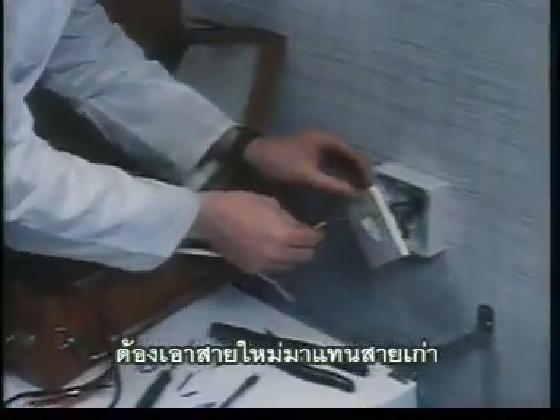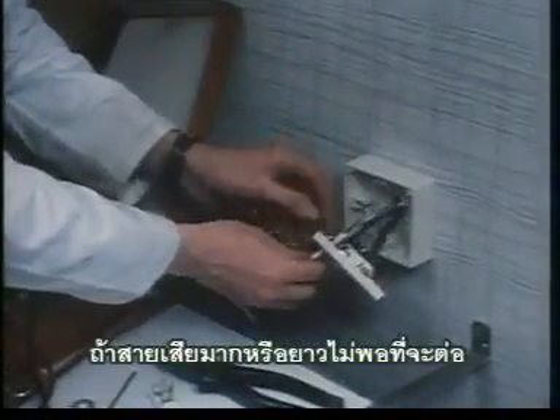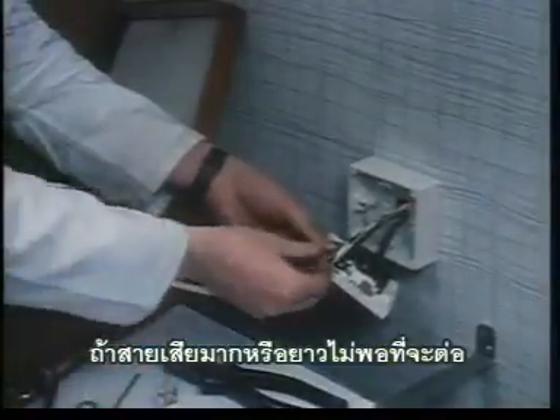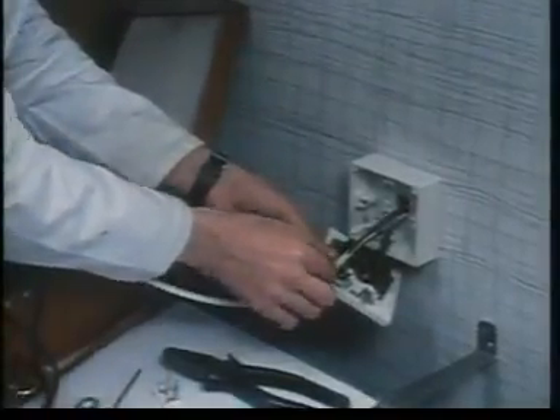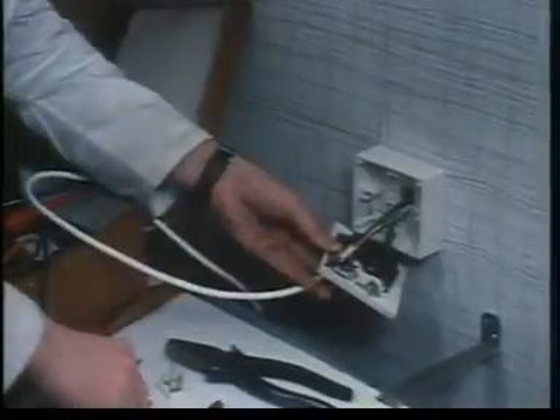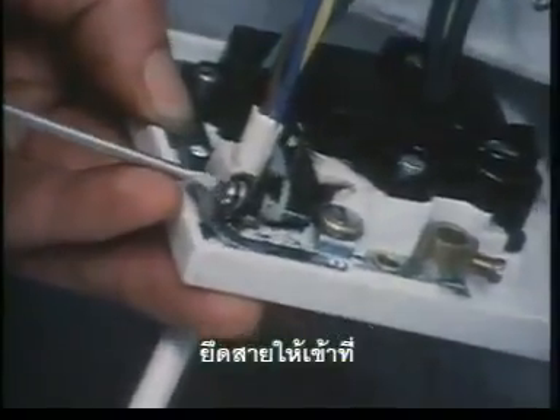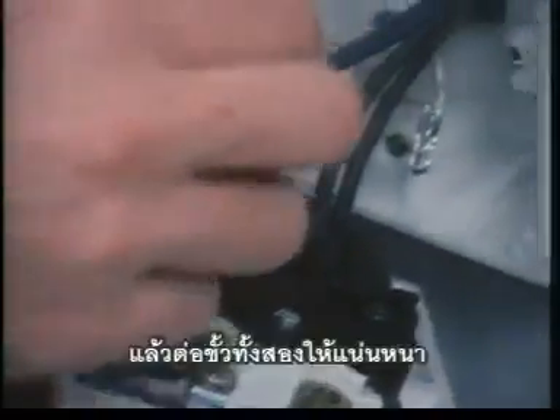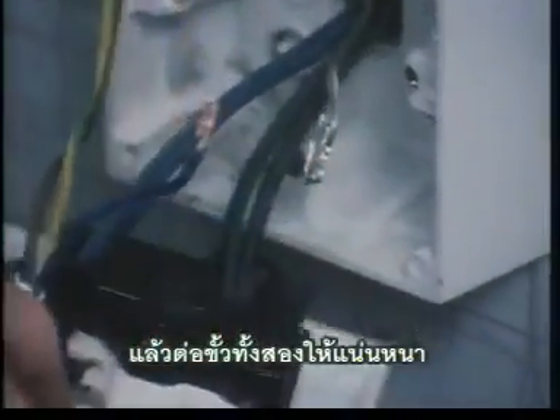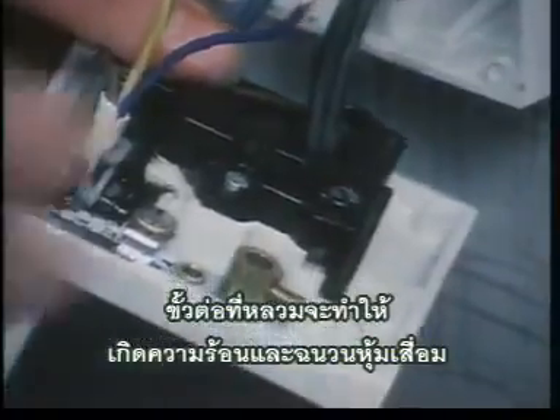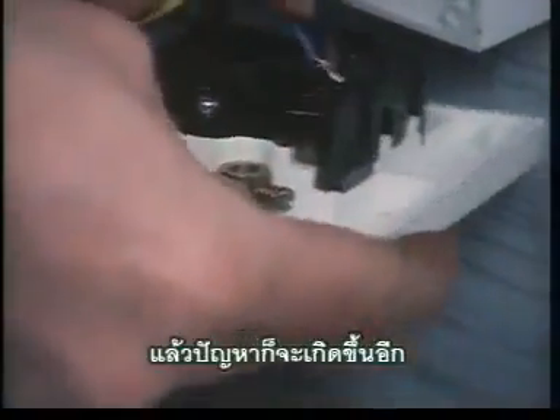A new cable must be used to replace the old if the damage is greater or if the length does not allow for safe reconnection. Now anchor the cable in place and then reconnect the 2 phases, ensuring tight connection. A loose connection will result in overheating and insulation deterioration, with further faults occurring.